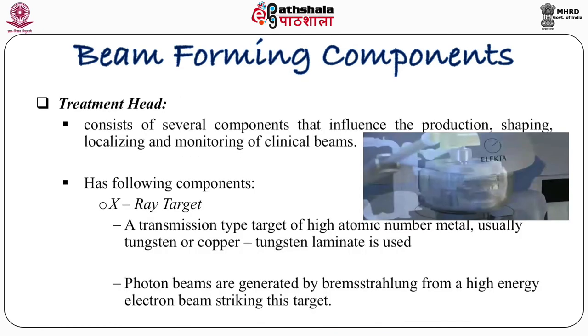The treatment head consists of several components that influence the production, shaping, localizing, and monitoring of the clinical beam. It has the following components. The X-ray target is a transmission type target of high atomic number material, usually tungsten or copper — tungsten laminate is used. Photon beams are generated by bremsstrahlung radiation from a high energy electron beam striking this target. When high energy electrons strike the target, photons are generated in the forward direction. The treatment head also contains a flattening filter. The bremsstrahlung radiation contains various energies from lower to high energy, with a peak at the most probable energy in the output of the linac.